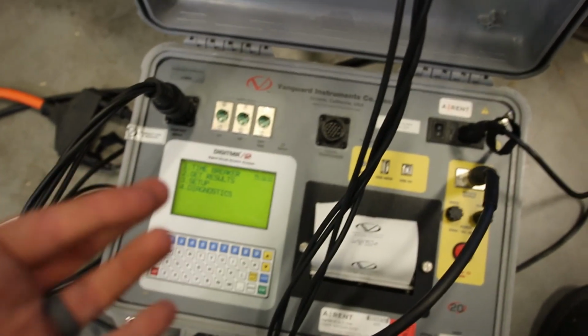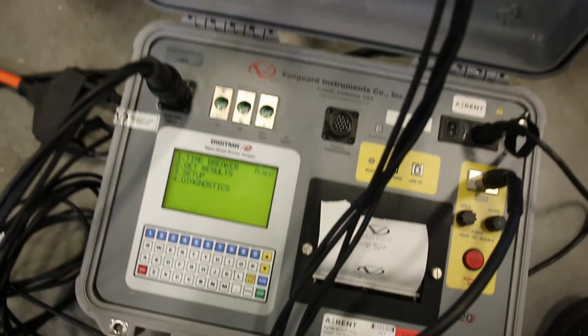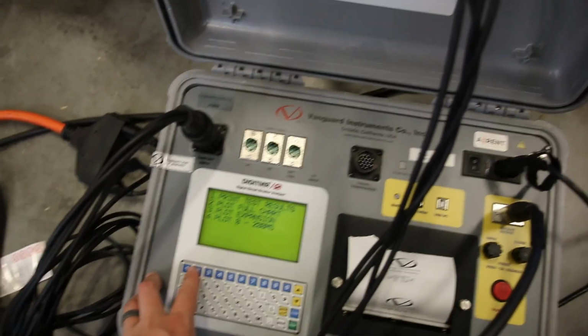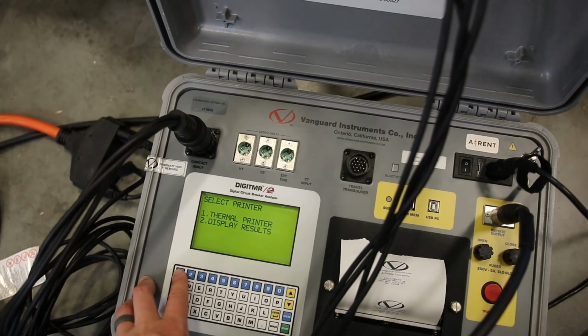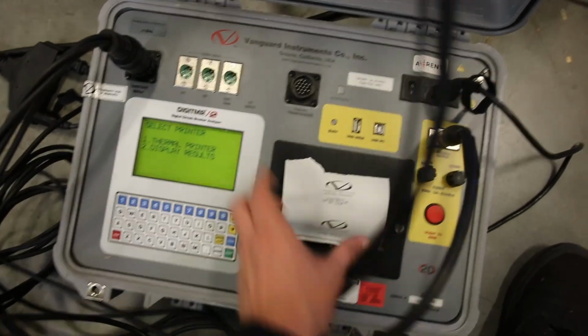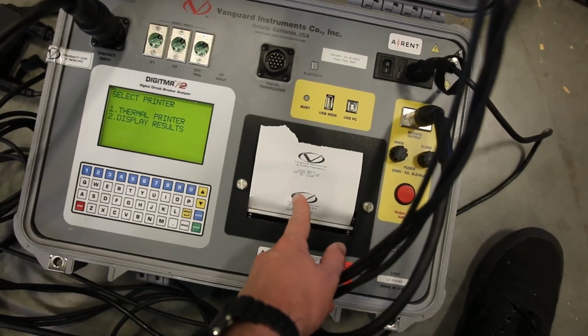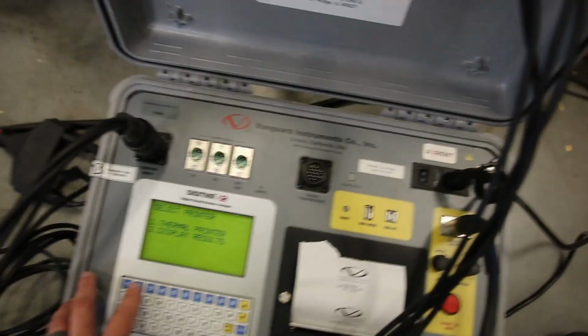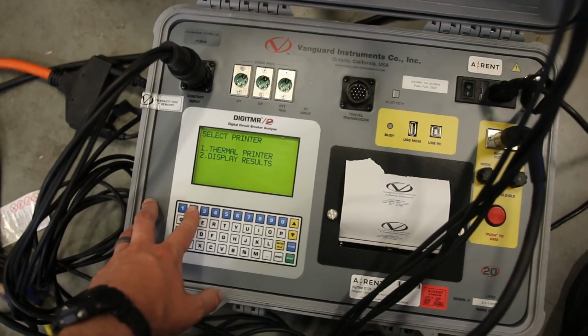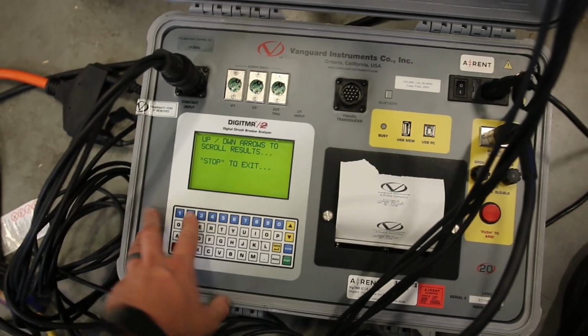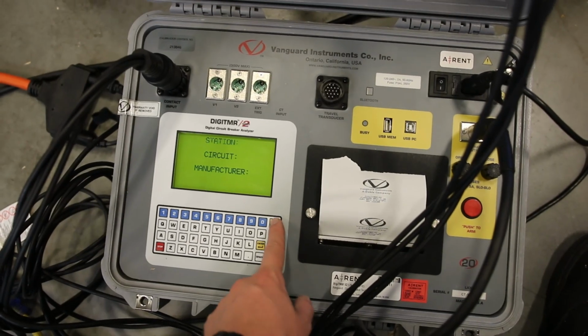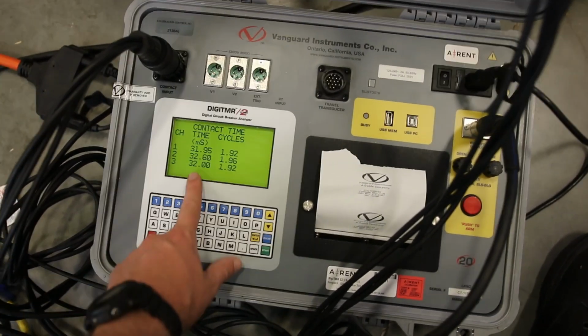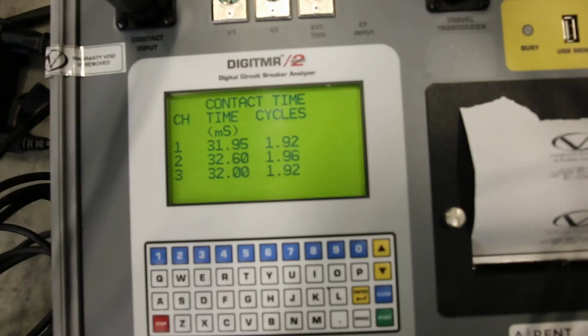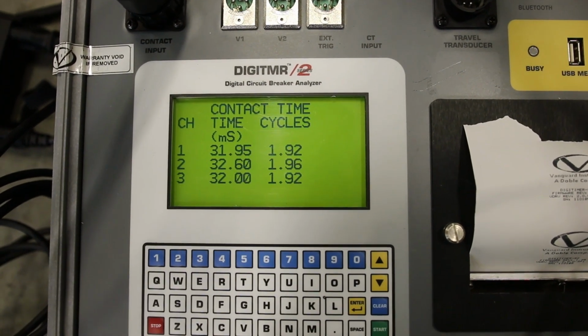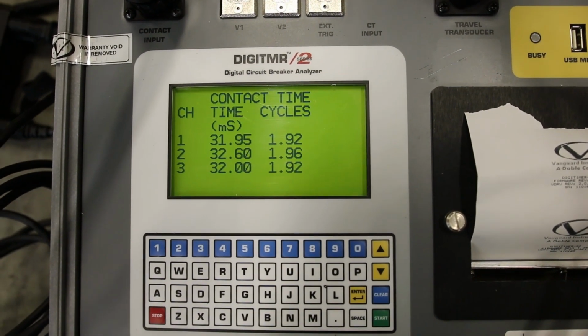All right, now pulling the results off of here, unless you're doing it on the software, obviously I'm showing you the quick and dirty way. We're gonna go get results, print test results, and then this has a printer on it, like a thermal paper printer, which I don't know why you would use, probably a holdover from an older test set. We're just gonna click display results and then scroll up until we find our result. There we go, that's our timing. So this operated in less than 2 cycles for all 3 poles.